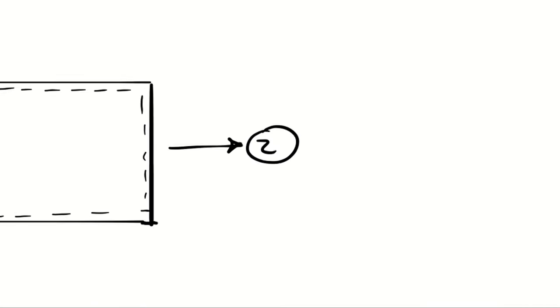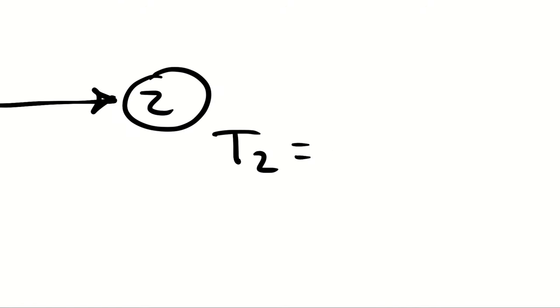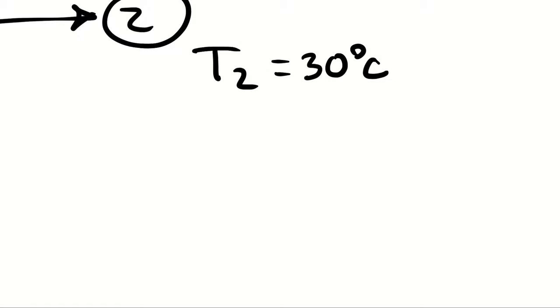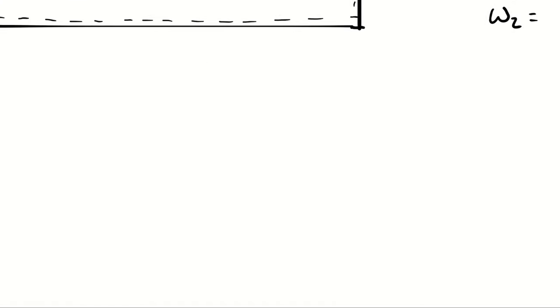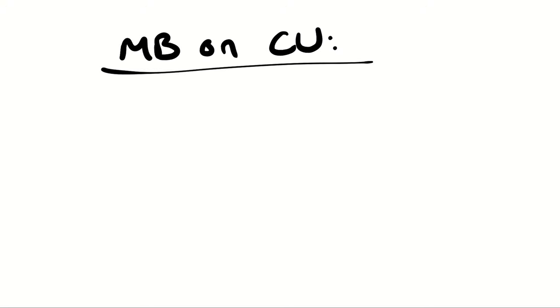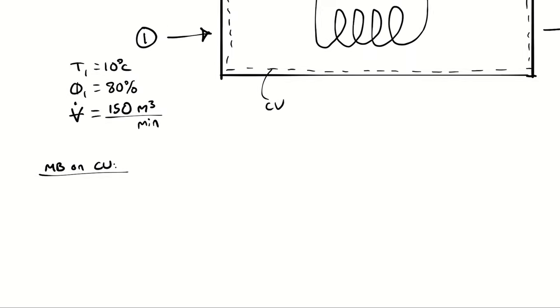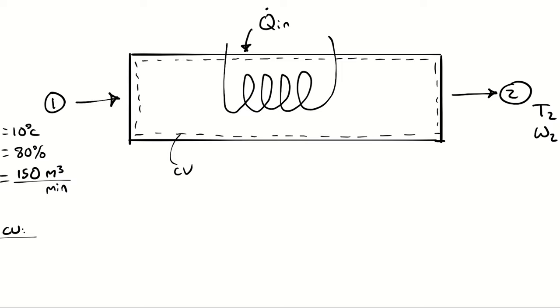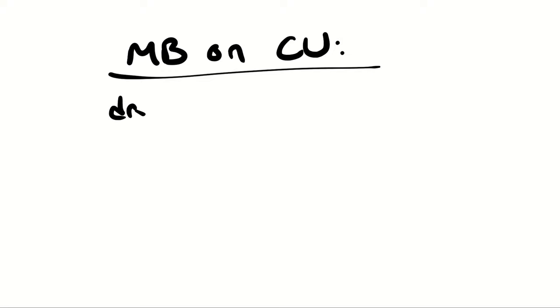At state 2, I know that the temperature is 30 degrees Celsius. I need two independent intensive psychrometric properties to fully define my state point, from which I can look up anything else. The other property comes from our mass balance. Just like in the adiabatic saturation chamber, I can set up a mass balance on the dry air, the water vapor, or the atmospheric air as a whole. The atmospheric air balance, generally speaking, isn't very useful.